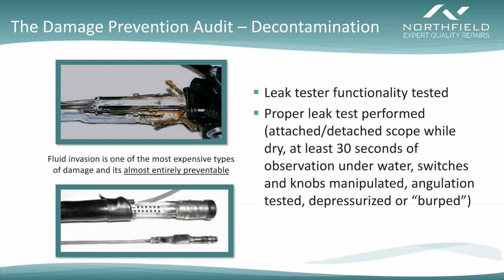We also want to see proper leak testing technique used. The specific steps will be outlined in the manufacturer's IFUs and may differ slightly depending on manufacturer and model. But the general rule is that the leak tester has to be attached and detached while the scope is dry. If you unplug the leak tester while the scope is submerged, you will flood your scope.